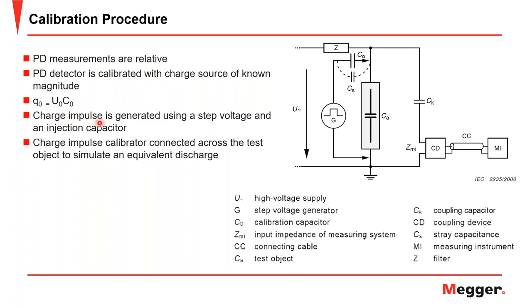In the chart, a charge pulse impulse is generated using a step voltage and injection capacitor. And the charge impulse calibrator is connected across the test object to simulate the equivalent discharge as stated here. So across the test object, you input a known charge, and that's what allows you to create the relation between the partial discharge activity seen once the calibrator is removed.